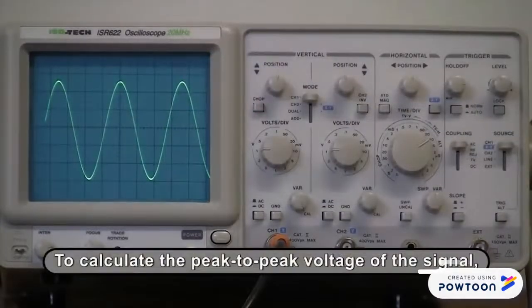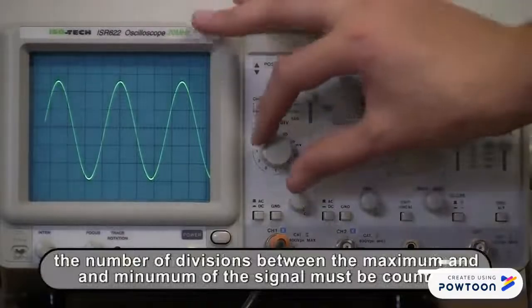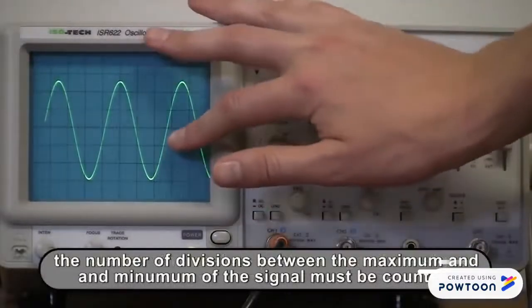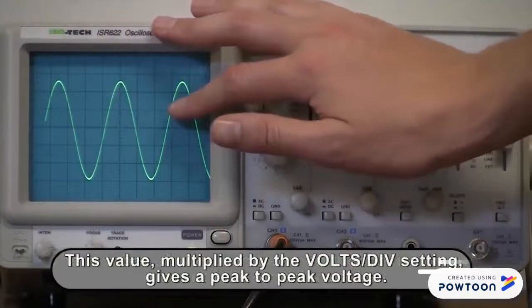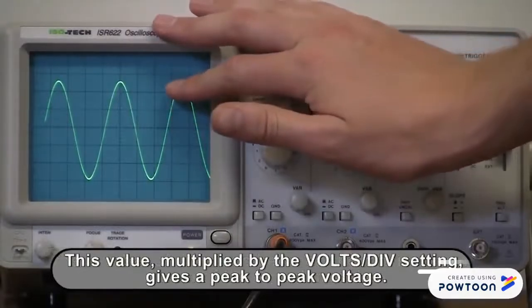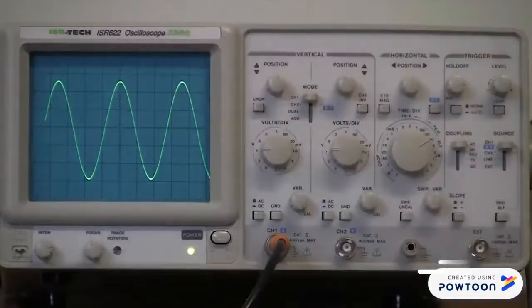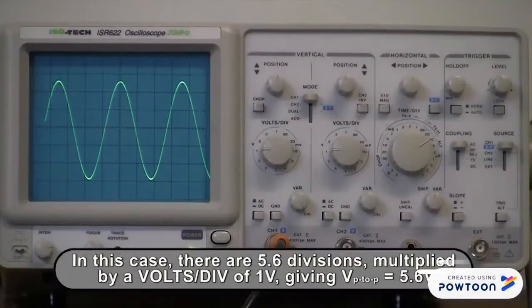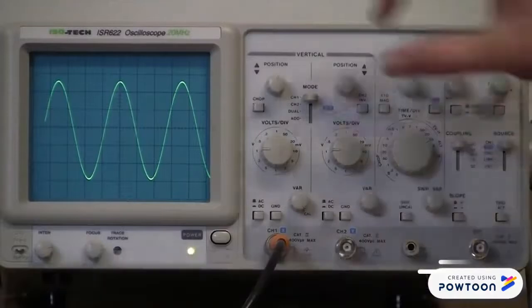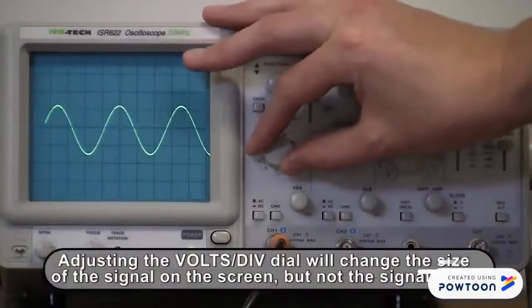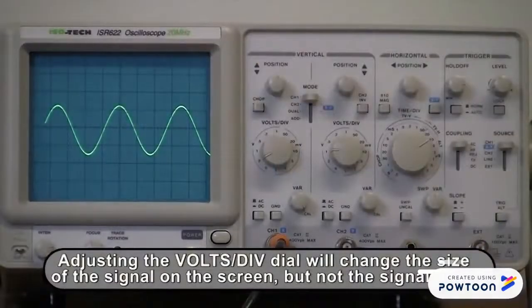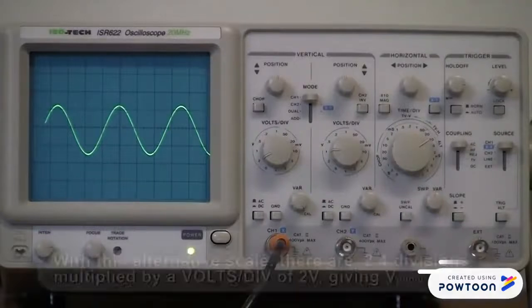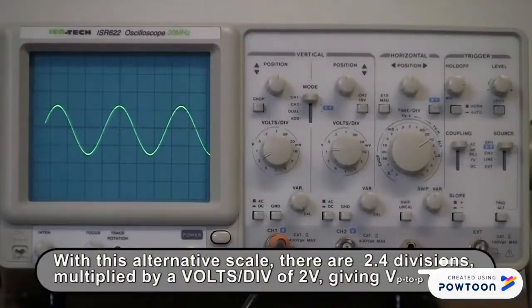To calculate the peak-to-peak voltage of the signal, the number of divisions between the maximum and minimum of the signal must be counted. This value, multiplied by the volts per division setting, gives a peak-to-peak voltage. In this case, there are 5.6 divisions, multiplied by a volt per division of 1 volt, giving a peak-to-peak voltage of 5.6 volts. Adjusting the volts per division dial will change the size of the signal on the screen, but not the signal itself. With this alternate scale, there are 2.4 divisions, multiplied by a volts per division of 2 volts, giving a peak-to-peak voltage of 4.8 volts.